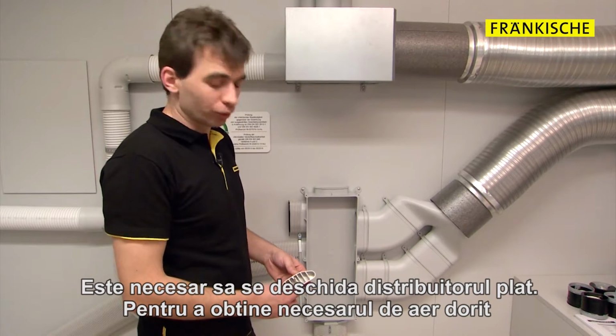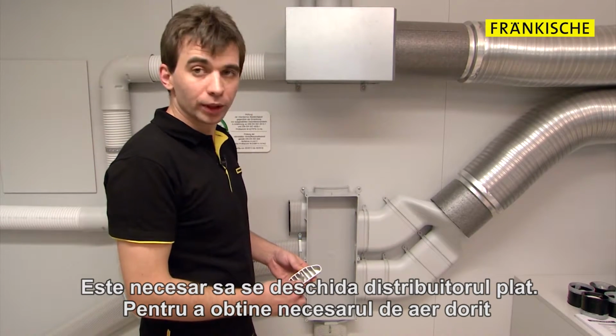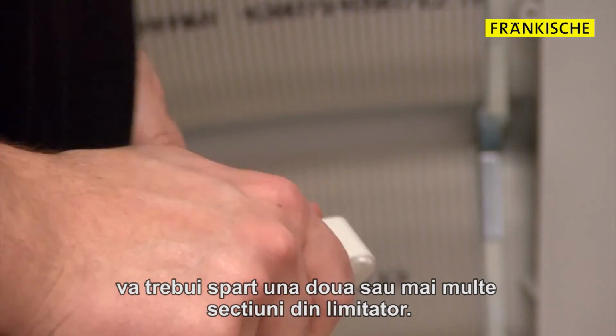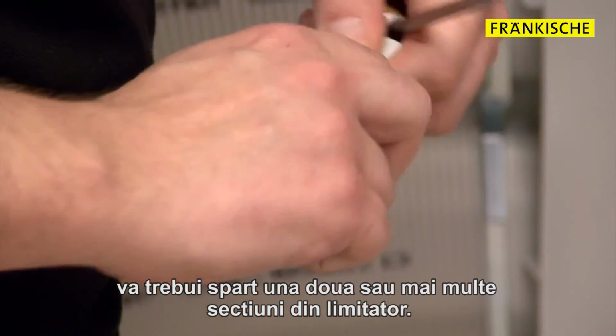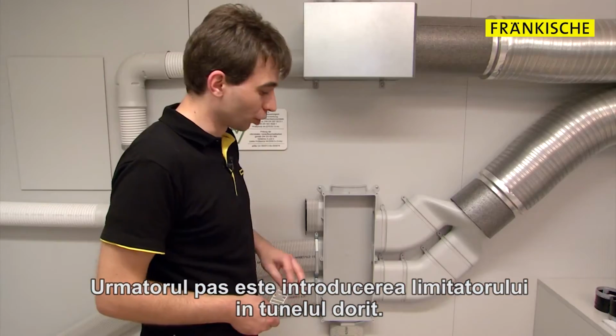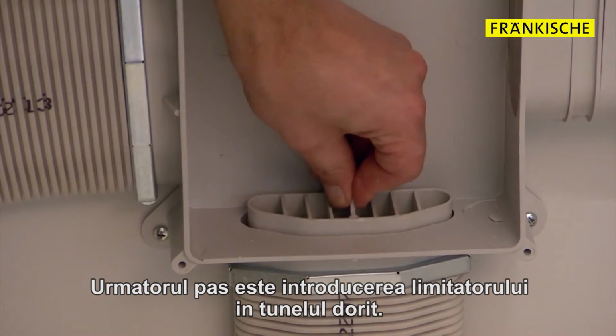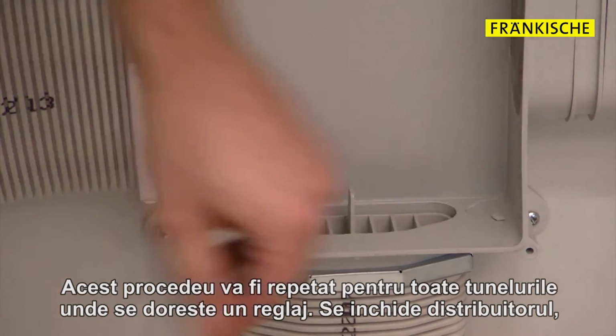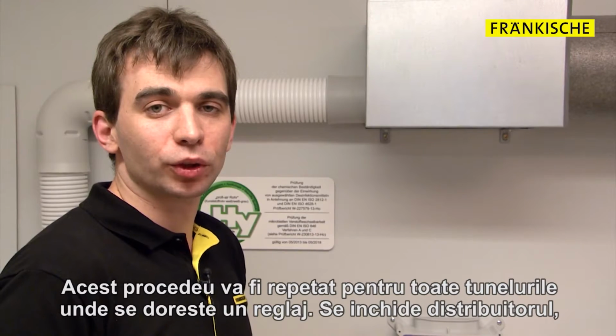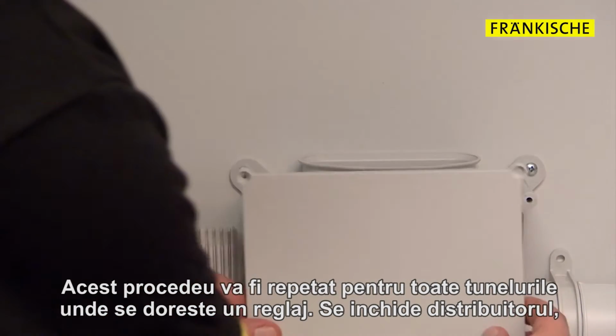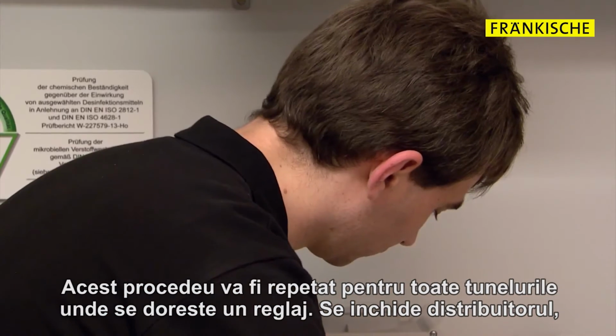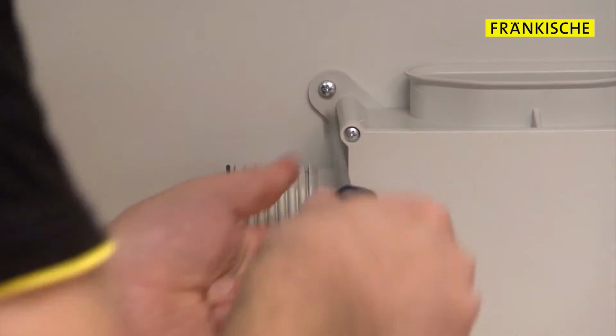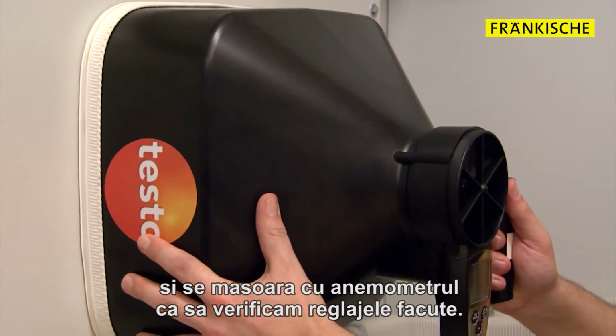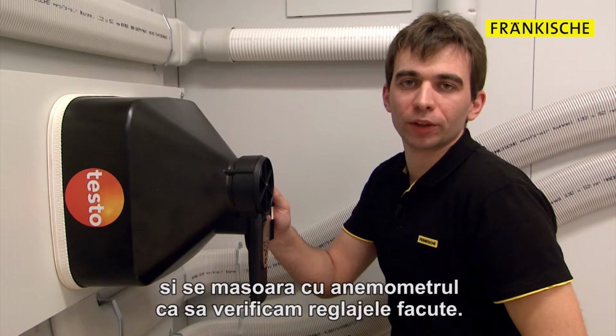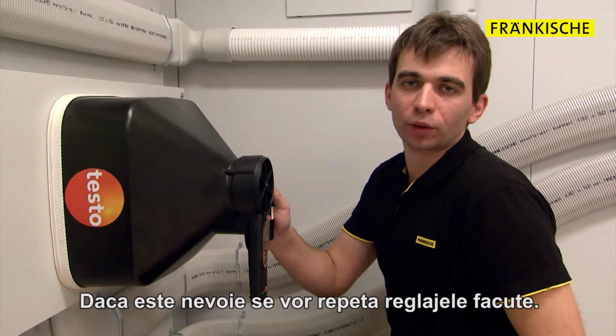The necessary openings for the air volume flow are broken out of the tunnel airflow restrictor. And in the next step, the tunnel airflow restrictor is inserted into the corresponding tunnel pipe. This procedure must be repeated for all necessary air connections. After that, the manifold must be closed again. Afterwards, use an impeller anemometer to check the adjustments made and, if necessary, adjust them once again.